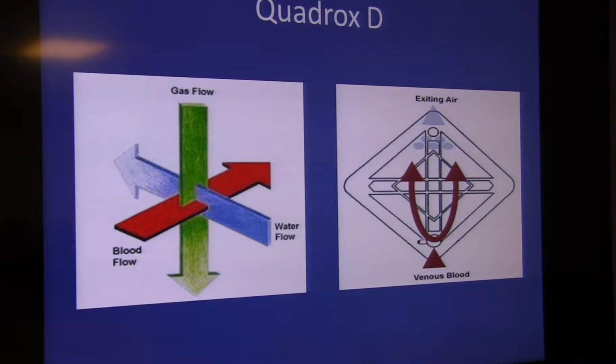You can remember either one of them. Usually you know that this one's the exhalation port, because just like you have condensation when we breathe out, there can be condensation when this breathes out as well. So if you touch the exhalation port of this, you'll realize that it's a little damp when you touch it. And there's no tubing, it's just open like that. And then, so you've got blood front to back, gas top to bottom, and the other job that this does for us is this acts as a heater.